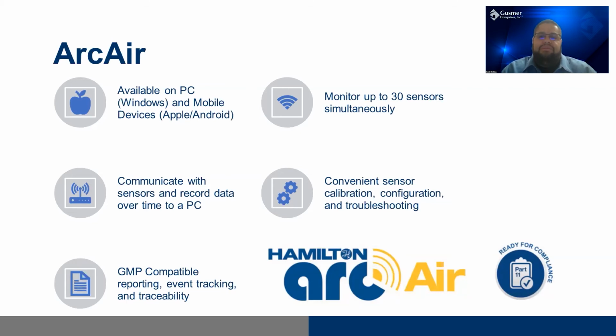You can monitor up to 30 sensors simultaneously using the software. You can also set up experiments in the software that allow you to track data. And this is on PC, but you can track data and record data for up to 3 months on 3 different sensors. So say you wanted to start an experiment, call it tank 1, you had a DO sensor in there, and you had a pH sensor in there, and maybe you had a conductivity or ORP sensor in there. You could select 3 different sensors for that tank and monitor that tank for 3 months. And you can then take that data and export it into CSV. So it's a really great tool to track your data. The data recording is on PC only, but you can still monitor and calibrate those sensors on your phone or tablet.